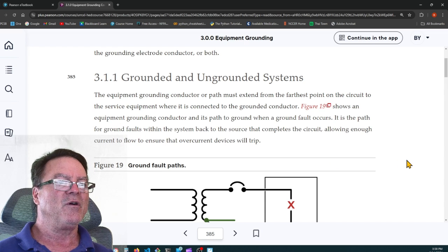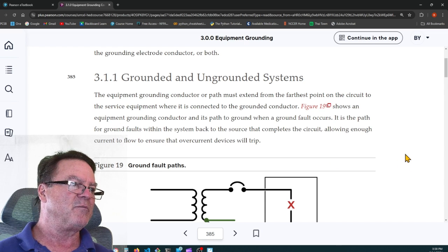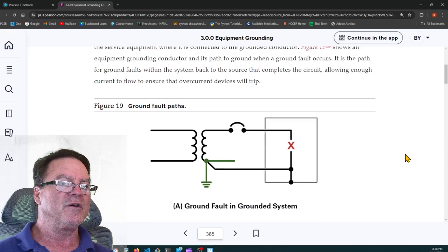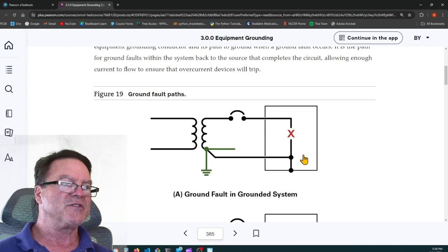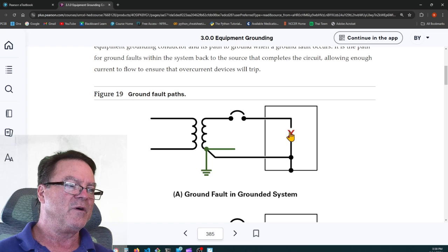It's the path for ground faults within the system back to the source that completes the circuit, allowing enough current to flow to ensure the overcurrent device will trip. So here's a fault on this box, and because this is grounded, it allows enough current to flow to ground that will trip that circuit breaker.